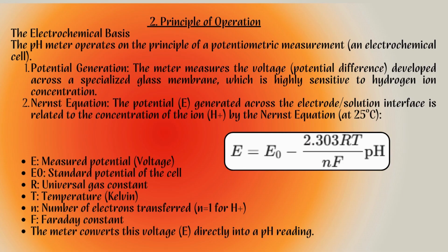Essentially, it functions as a tiny electrochemical cell. The key component here is a specialized thin glass membrane at the tip of the electrode. This membrane is highly sensitive to the concentration of hydrogen ions both inside and outside the electrode. When the electrode is placed in a solution, the difference in hydrogen ion concentration on either side creates a tiny voltage or electrical potential across the glass membrane. The meter measures this voltage difference, and that potential is mathematically linked to the pH by the Nernst equation.